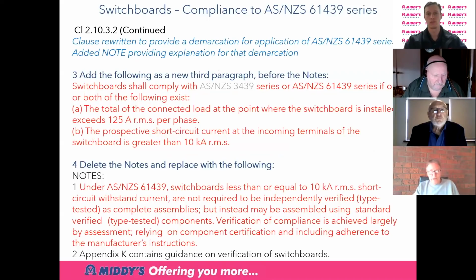Switchboards shall comply with the 3439 series if both of the following exist. This is all new, by the way. A, the total of the connected load at the point where the switchboard is installed exceeds 125 amps RMS per phase, or B, the prospective short circuit current at the incoming terminals of the switchboard is greater than 10 kA RMS. We delete the notes and replace the following under the AS/NZS 61439 series. Switchboards less than or equal to 10 kA RMS short circuit withstand current are not required to be independently verified, type tested as complete assemblies, but instead may be assembled using standard verified type tested components. Verification of compliance is achieved largely by assessment, relying on component certification, including adherence to the manufacturer's instructions.